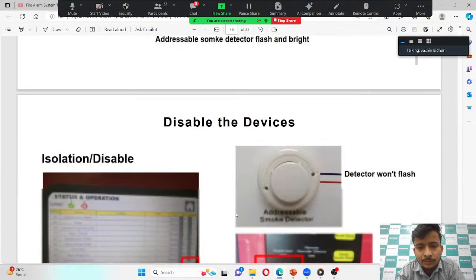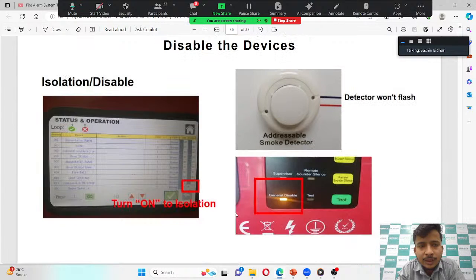If you isolate or disable that device from that loop, the panel will display the general disable LED, and the device will be completely off, meaning it will not flash anymore. The device's LED will not flash.